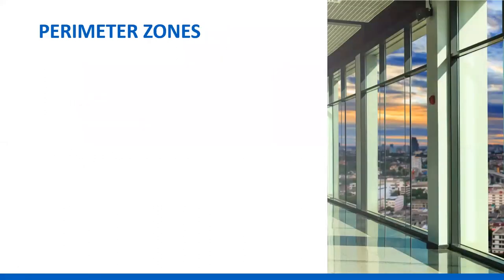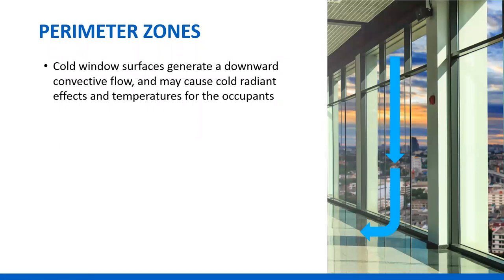Loads are a lot less in perimeter zones than they used to be because we got better glass. But the cold surface generates a downward convective flow and may cause cold radiant effects for occupants. There's some debate about the radiant effect. When ceiling heating is used, the ceiling gets warm and offsets the cold window — the mean radiant may be neutral in a lot of perimeter zones.